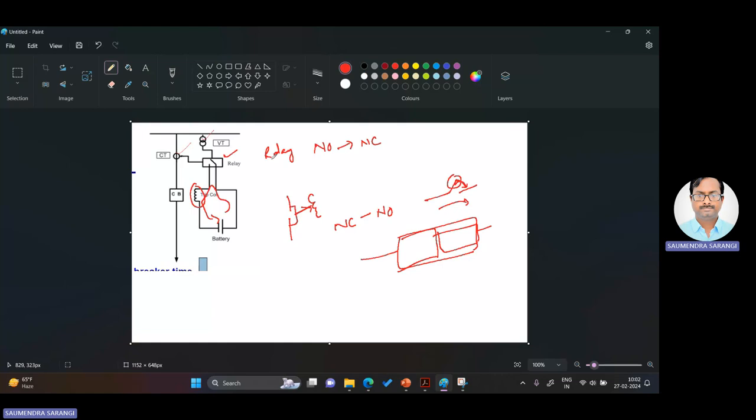So it happens within a chamber. Whenever we are trying to take the movable contact back, sparking will come, but the sparking has to be extinguished by reducing the number of charges here. So how are we doing that? Suppose we have air, and we make the air flow through this at very high speed. So what will happen? All the charges we have here will be evacuated, so the sparking will die down.